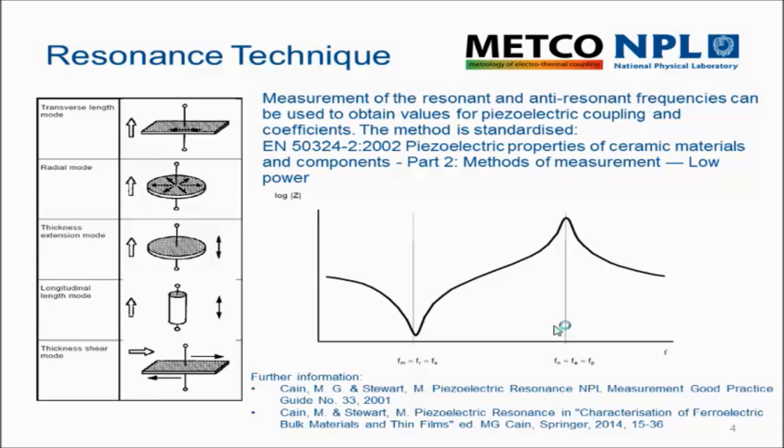The standard specifies a number of geometries which enhance particular resonant modes, and those different resonant modes can be used for deriving different parts of the piezoelectric coefficients. Typically there's a transverse length mode for measuring D31, a radial mode, a thickness extensional mode, and a longitudinal length mode which emphasises the 33 movement, and a shear mode resonator as well. There's quite a lot in the standard, and also in the original IEEE standard which preceded it. NPL have also published a number of reports on some of the techniques.